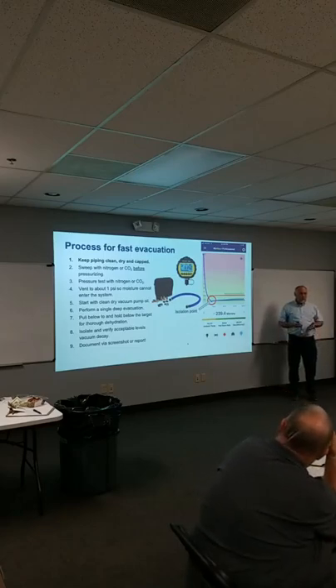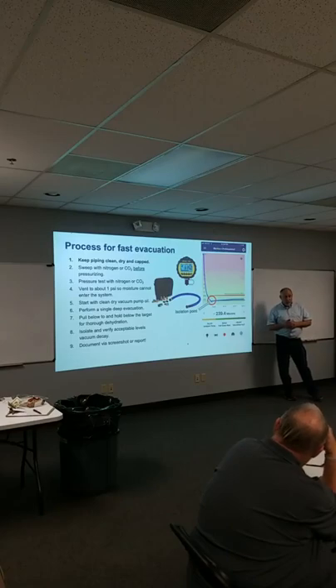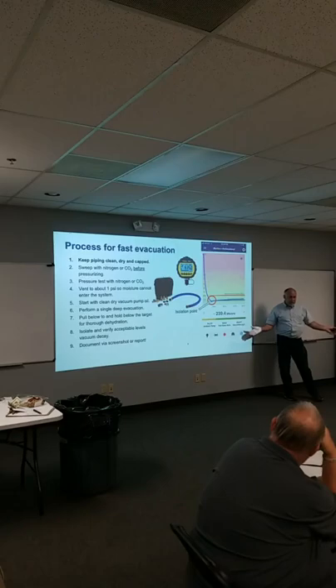Nitrogen. Our air is 79% nitrogen, right? Everybody knows that. If you have a system that's been open to atmosphere, the last one of these that I had a big problem on was a big variable refrigerant flow system. It had maybe 100 heads on it, right? The guy puts in all this piping, miles of piping. So from the factory, they say we're going to test all this piping. They take the pressure up to 600 PSI.